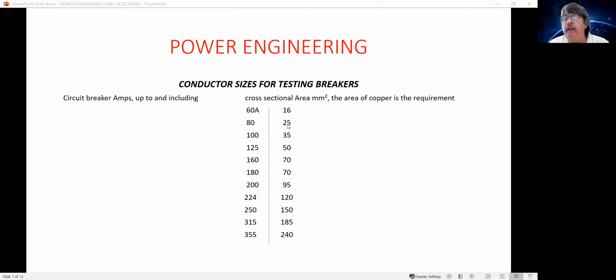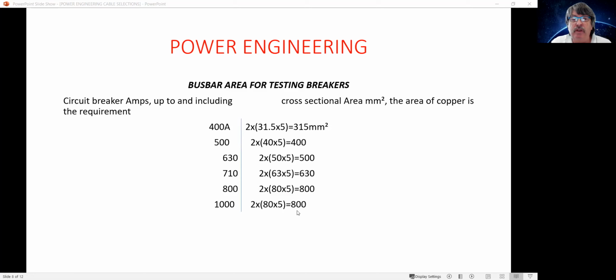Specifically, and we talk here very specifically to circuit breakers which are of a thermal type mechanism. So anything that uses heat and we vary the conductor has a potential to change the characteristics of that circuit breaker. You've got both things. You've got the normal cable size type arrangement, and you've got some bus bars. So what the circuit breaker manufacturer has to do is test any of these breakers with those size levels. And I've included here millimeters squared on the bus bars, because obviously you do get a variation on the bus bar widths and thicknesses, etc. And the net effect is that you need that millimeters squared as opposed to the actual level, although obviously surface area could play a part in here.